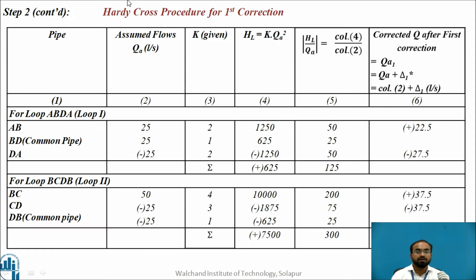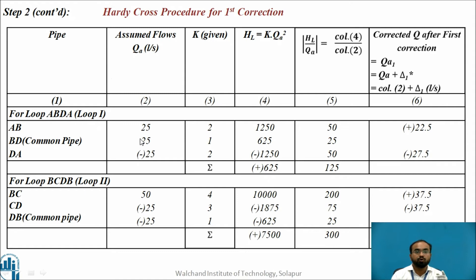Column 2 contains the assumed flow rates calculated earlier, including signs — clockwise positive, anticlockwise negative. Column 3 is the K value, and column 4 is HL using the formula K into Q squared. I know K from column 3 and Q from column 2. For every loop I take the summation: for loop 1 the summation of HL is 625, and for loop 2 it is 7500. Then I calculate HL divided by Q(A) in absolute form — for AB it is 50, for BD it is 25, for DA it is 50, giving a summation of 125. For loop 2 the summation of HL by Q(A) is 300.